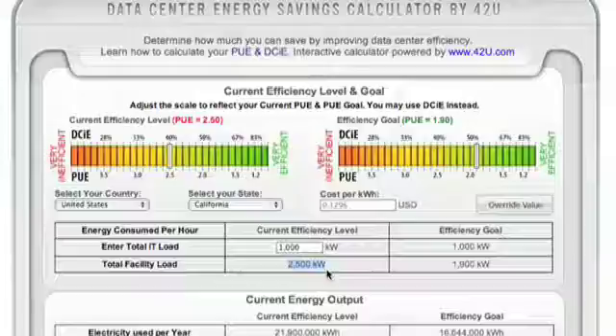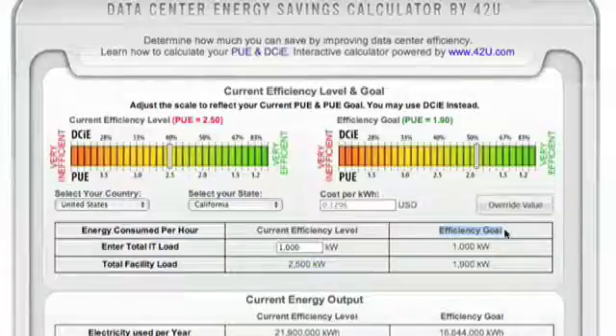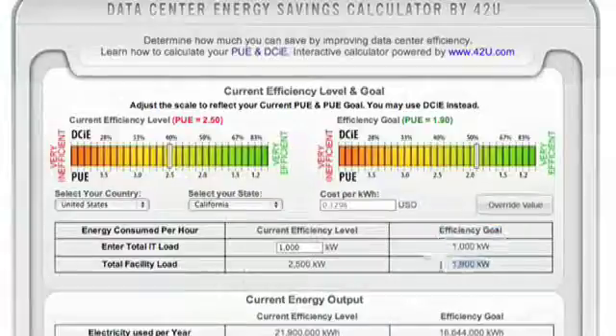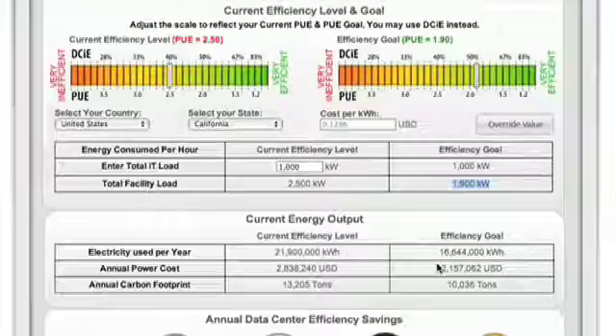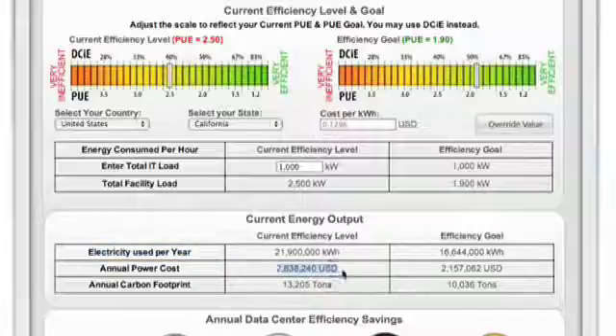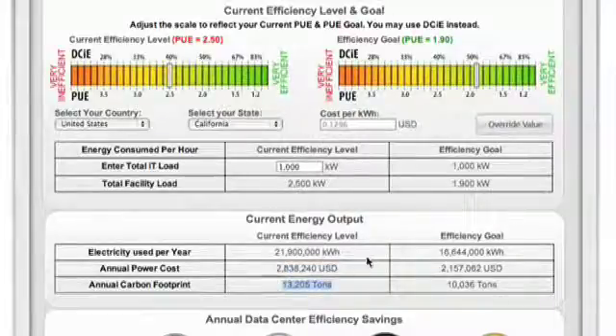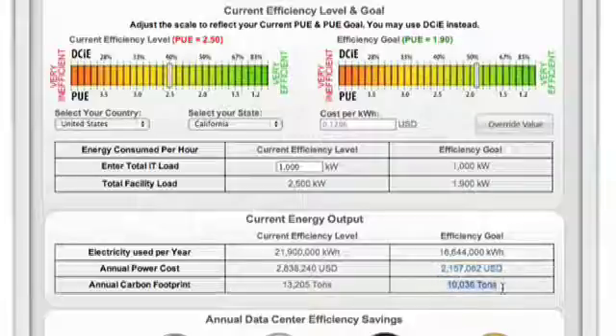From this value, the calculator also populates the efficiency goal. At our goal PUE of 1.9, our total facility load will decrease to 1,900 kW. The IT load is the last piece of user information the calculator requires. From these values, the calculator projects your total electricity use over 12 months, your corresponding annual power cost, and your annual carbon footprint for both your current state and your efficiency goals. You'll notice the decrease in electricity used, considerable cost savings, and the greater than 10,000 ton reduction in your carbon footprint.